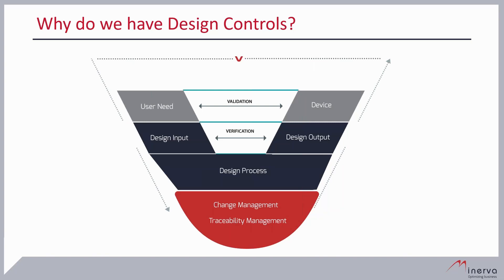The next slide shows the same content in the V-model, showing the relationships between elements. The left side of the V-model relates to design activities and data needed for them, while the right side relates to the results of the design. The design process takes the design input from the left side and generates the design output on the right side. Conformance of the design output is checked by verification, and validation checks the device definition against user requirements. All of this is covered by change management, which gives us traceability for all the data in that process.